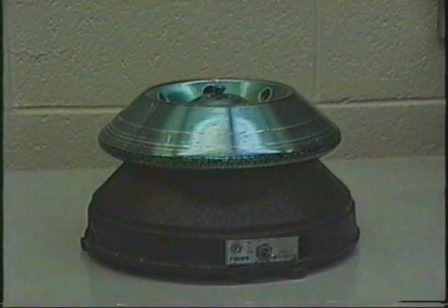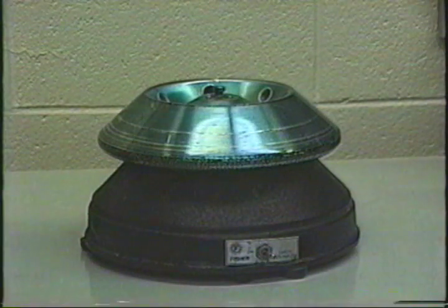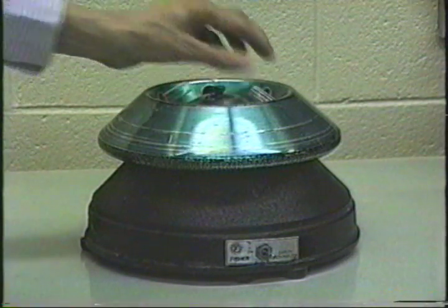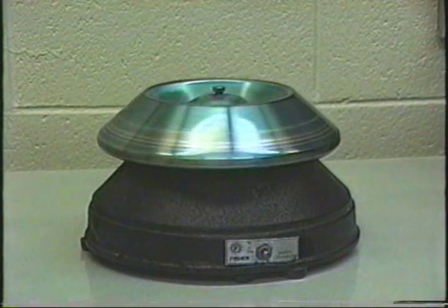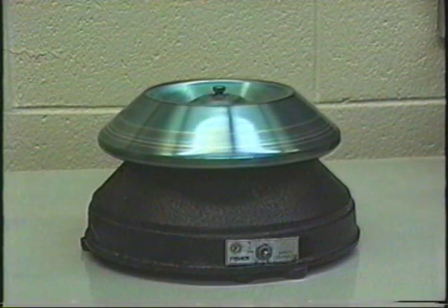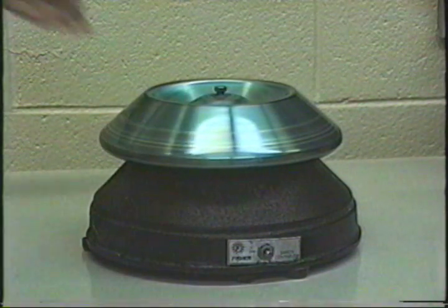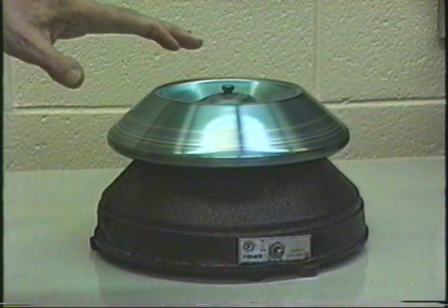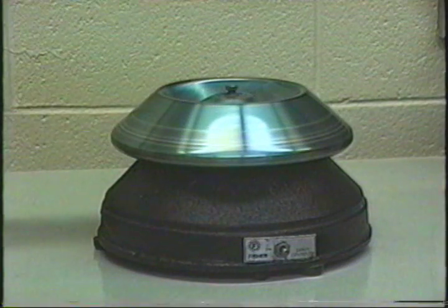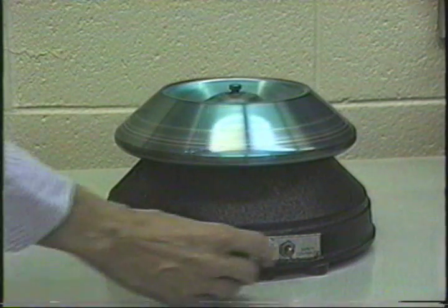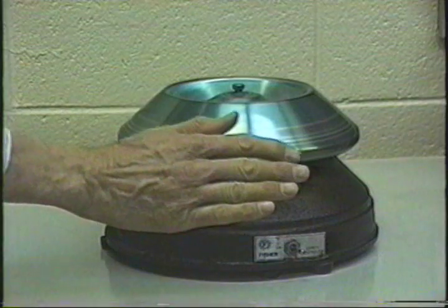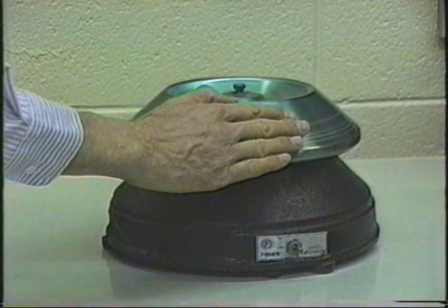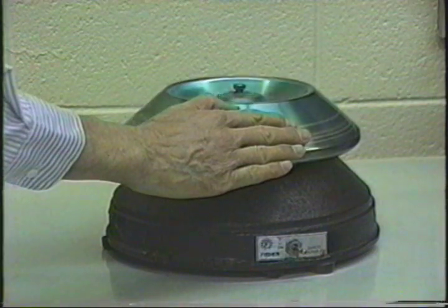All right, let's go over that one more time then. Make sure that when you put something in the centrifuge, you put a counterbalancing tube in. Then when you turn it on, make sure you keep watching it so that the centrifuge doesn't tend to wobble. Make sure it doesn't touch anything such as the cord. Keep your hands away from the centrifuge while spinning, particularly on the top here. And then when you turn it off and you want to slow down, make sure your fingers are in the direction of the spin, and then just lightly, gently slow it down.